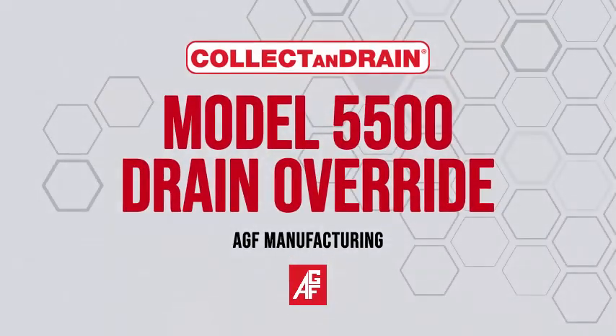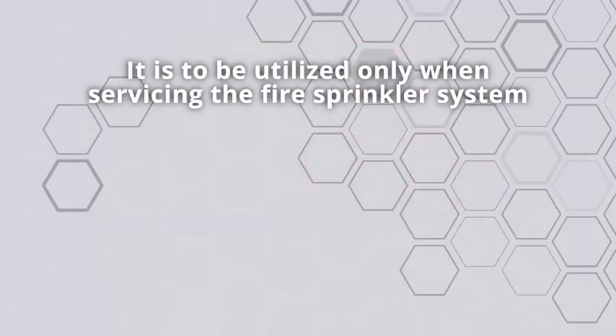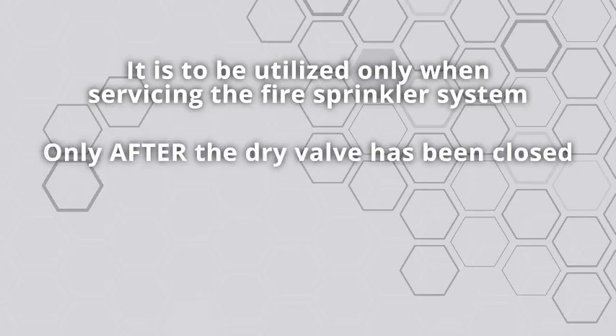The drain override feature is used to open the drain valve while the supply valve is open. It is to be utilized only when servicing the fire sprinkler system, and only after the dry valve has been closed.